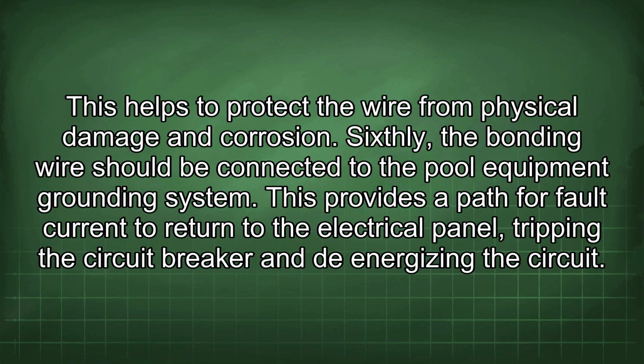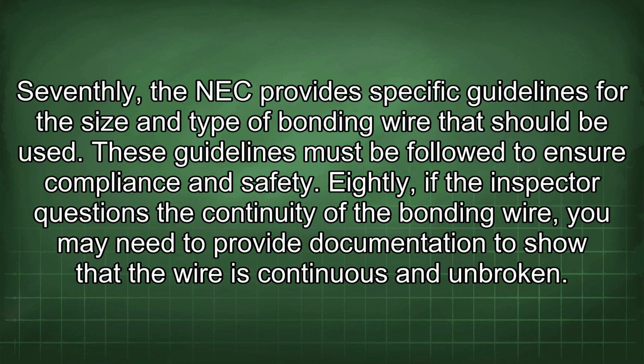This helps to protect the wire from physical damage and corrosion. Sixthly, the bonding wire should be connected to the pool equipment grounding system. This provides a path for fault current to return to the electrical panel, tripping the circuit breaker and de-energizing the circuit. Seventhly, the NEC provides specific guidelines for the size and type of bonding wire that should be used.